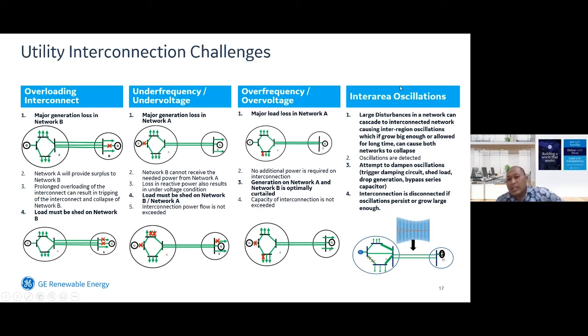The last one is related to inter-area oscillation. Large disturbances in a network can cascade to the interconnected network, causing inter-region oscillation, where if it grows big enough or lasts for a long time, it can cause both networks to collapse. So how do we solve this issue? We can attempt to dampen the oscillation by triggering a damping circuit, shedding the load, or dropping the generation, and also by having a bypass series capacitor. When the treatment above does not work, the interconnection should be disconnected. So this is the solution to dampen the oscillation that happens in the system.